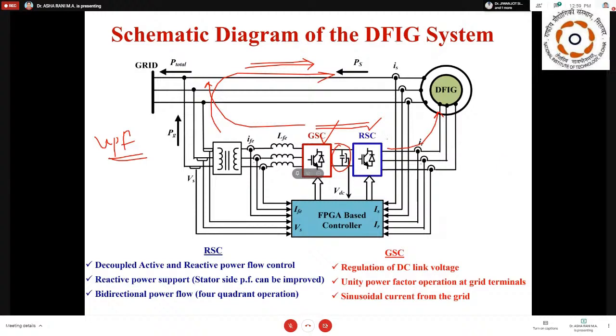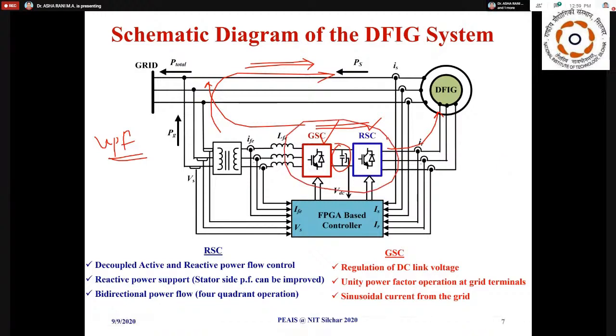Now, these converters are capable of handling only 30%. They cannot handle this infinite current and infinite voltage. Obviously, when large voltage and current are coming, the product, the overall power, is high, which means the capacity of the converters is not enough to handle that, and immediately the rotor side converter will burn. In order to avoid that, in industry what they do is connect these three legs through a resistance. That is generally called a crowbar. Once something like that happens, the power electronic switches inside will be activated based on the voltage and current, so that immediately the DFIG is connected through the rotor crowbar and grounded, and the device can be protected.